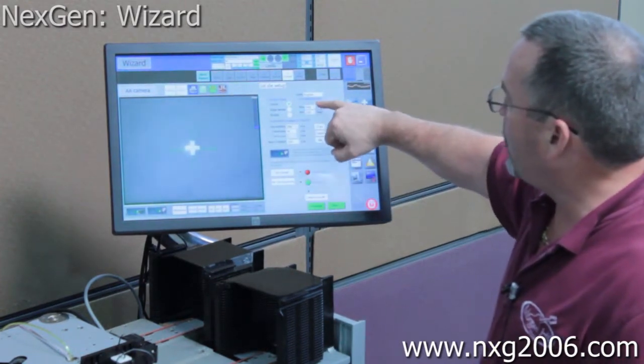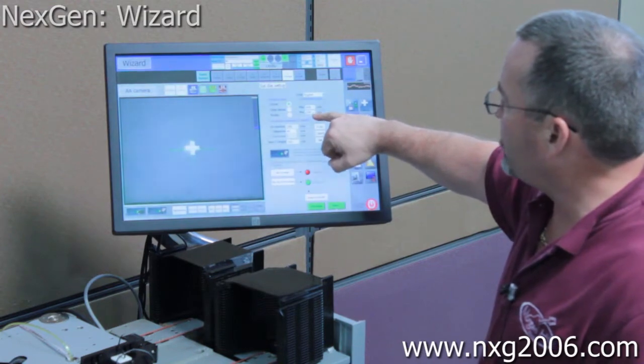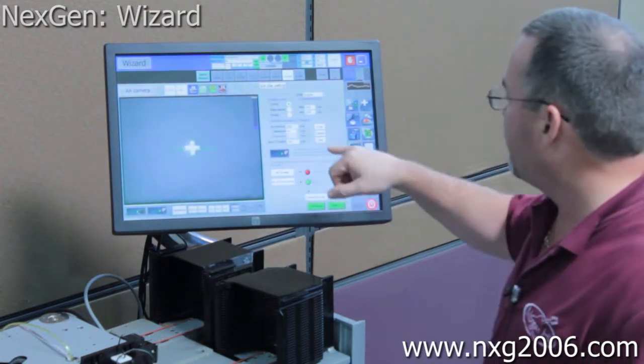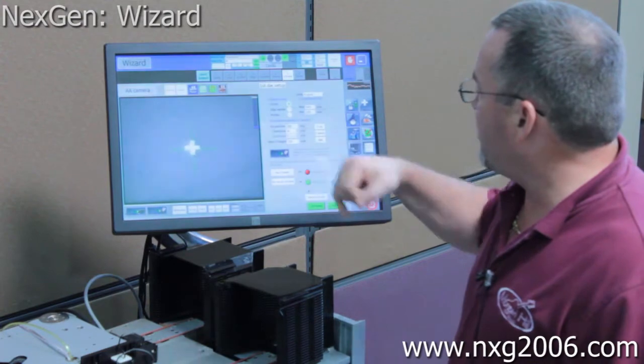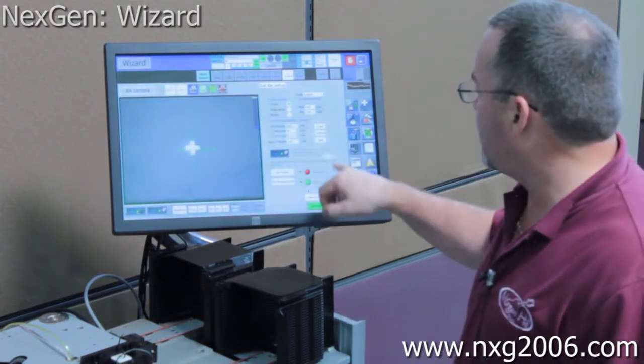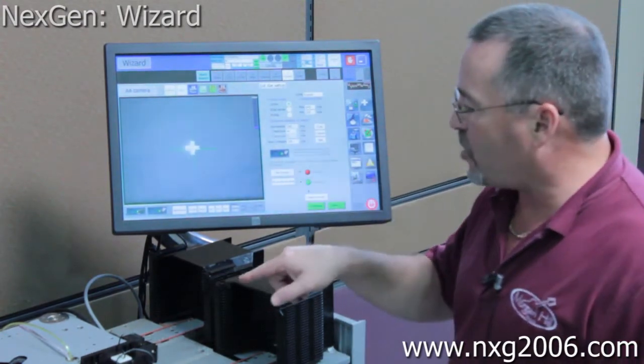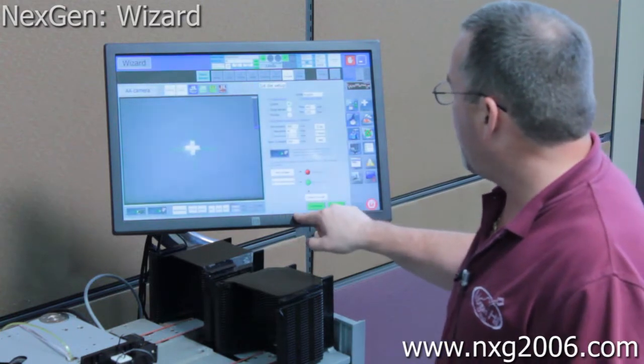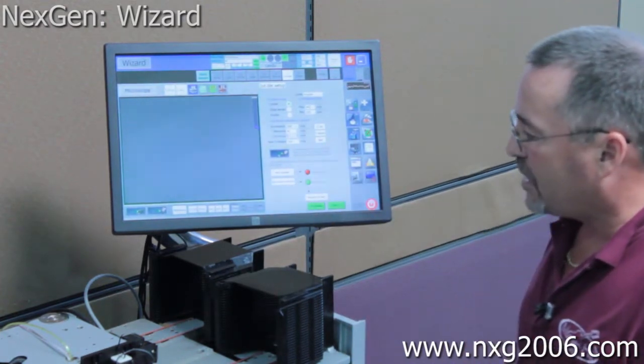We have a maximum height of 400 mils and a minimum height of 200 mils. So that's our typical operating range. The up position right now is at 200. We have a 40 mil clearance, and Z height set at 200. So at this point, we want to drive the wafer underneath the probe card. So we're going to go ahead and move to the microscope area. It's going to sit under there.